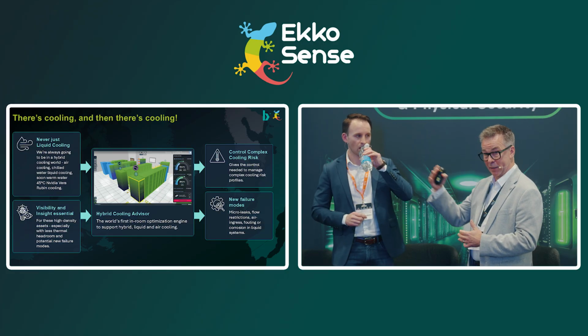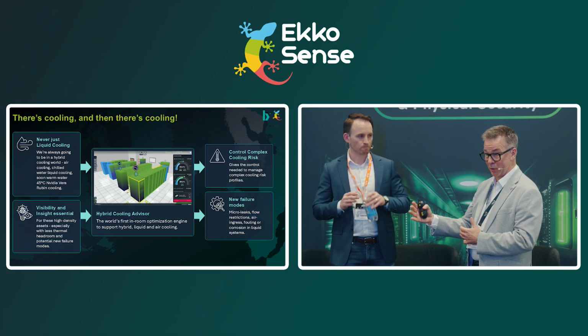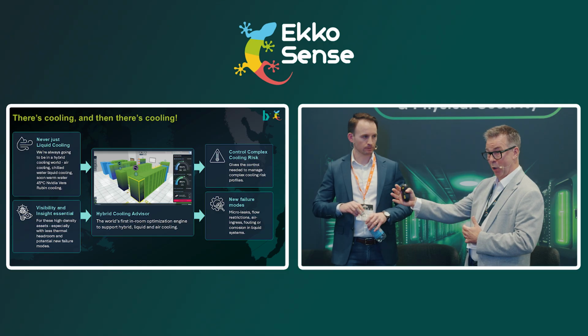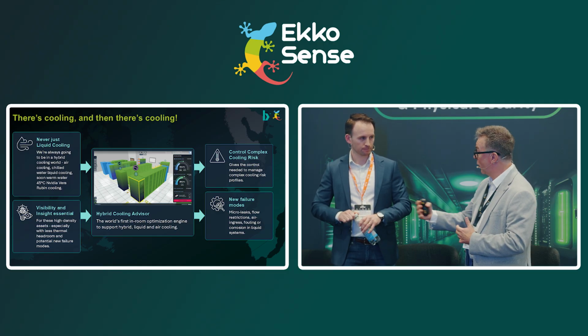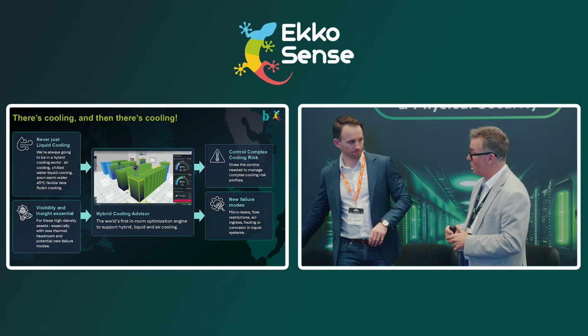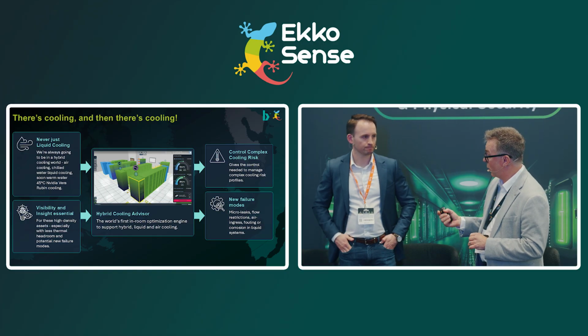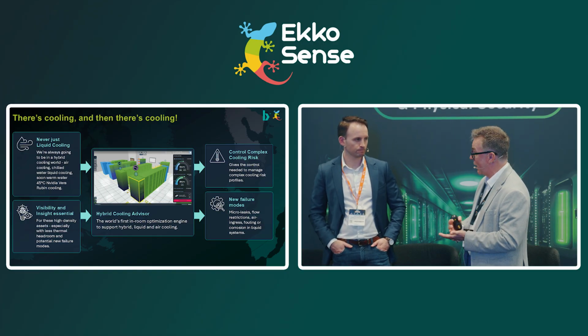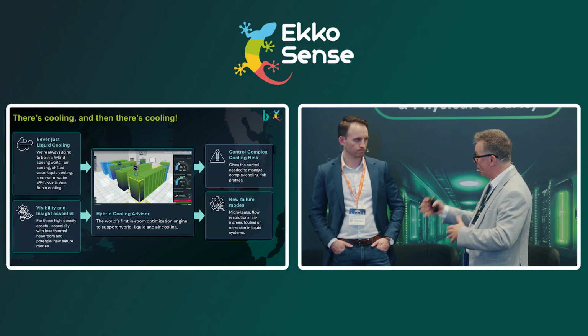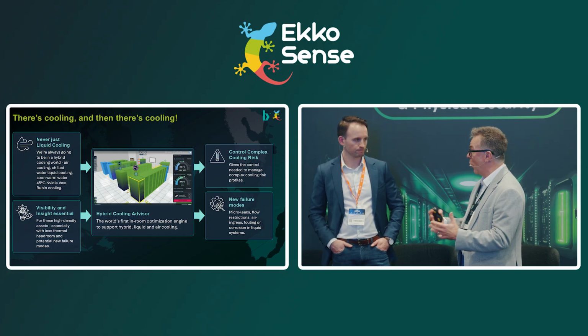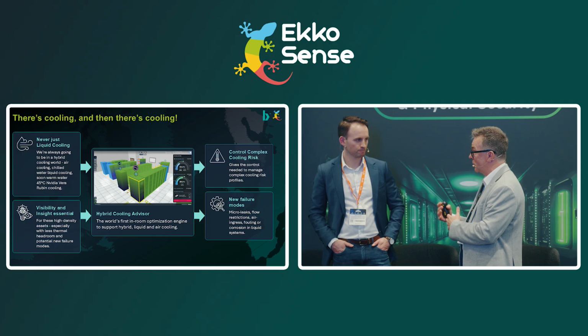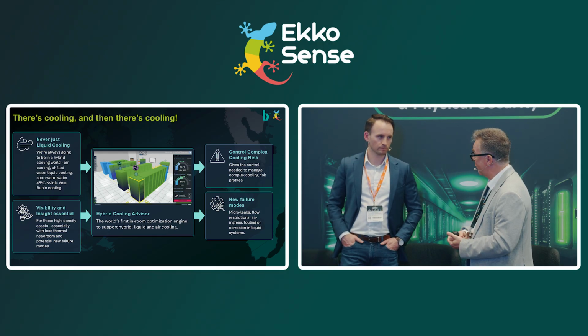We're looking at things like the IT load and the cooling demand, matching cooling demand with exactly what's needed, so we're not overcooling or undercooling, we're hitting those sweet spots. We've also introduced new failure modes that pick up things like micro leaks, flow restrictions, air ingress - minimal things you might not necessarily pick up in a traditional BMS system, giving much better granular visibility.